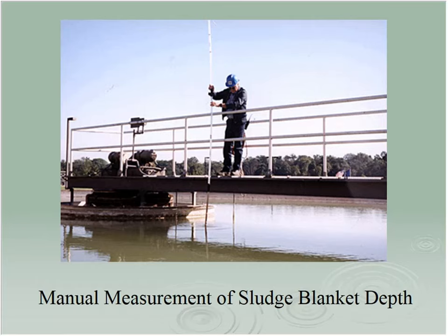So yeah, we carry a sludge blanket, and we need to keep track of where this thing is. We have measurements on this, and a lot of them were done manually with this big plastic tube called a sludge judge. You put sections together, as many as you need, so you can reach the bottom. It's a clear plastic tube, and you go out to a certain location on the bridge, but people do it in various places. As long as everybody does it in the same spot the same way, it's no big deal. It's when somebody's doing it in a different place that it confuses things.